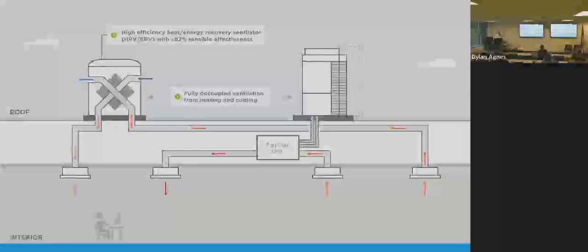Briefly on the concepts of very high efficiency DOAS, decoupling the ventilation air from the heat pump and spacing the applications, commercial applications makes a lot of sense. You can optimize each of those systems. Adding exhaust air energy recovery is an absolute no-brainer and a win even in more mild conditions, but especially in colder or hotter climates. There's a lot of ventilation load in some commercial buildings, especially higher density occupied ones. And when you can get that heat or that heat rejection for free, it takes a lot of load off your heating and cooling system. It allows you to select an appropriate size and a cost-effective heat pump system, even in cold climates. So when you can cut out 30% of your design heating load, you can size a smaller piece of equipment that can still hold up, and you don't have to have 150% capacity just for that 1% of the year.